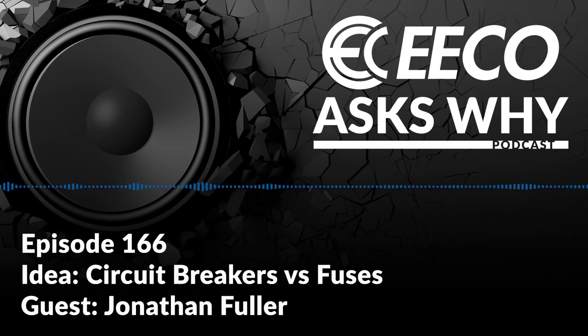Right. Absolutely. And that ties back to what we talked about in previous episodes, making sure you have the right coordination too, because you don't want to trip a breaker upstream versus the breaker that's closest to the device, or closest to the fault. Right, because then you could end up taking down half your facility just because you didn't have proper coordination. Instead of tripping the breaker right at the source of the fault, before that motor circuit or whatever it might be, you could take out something upstream that's providing power to five or six different circuits or panel boards.